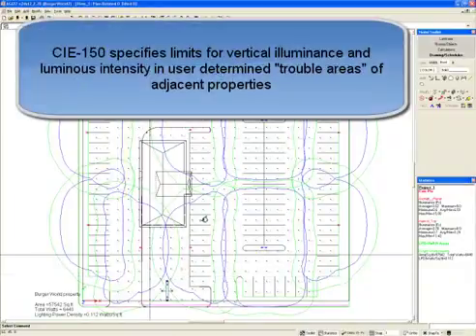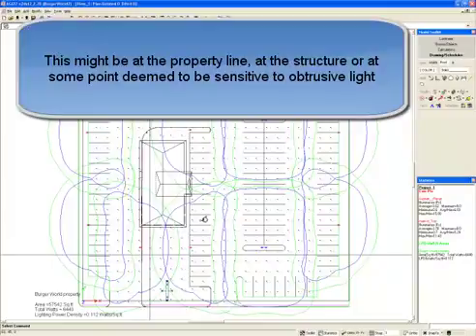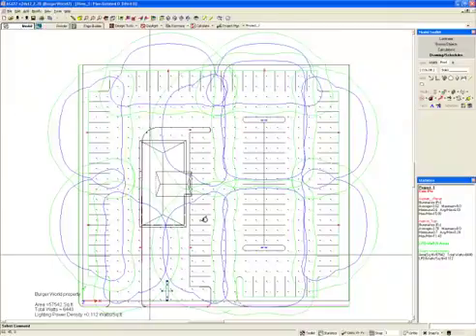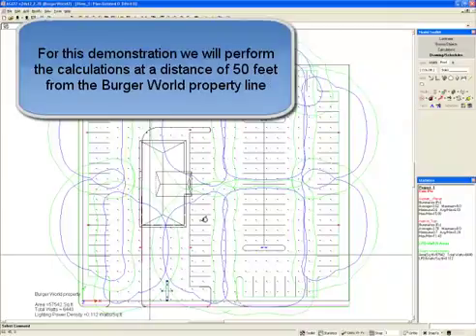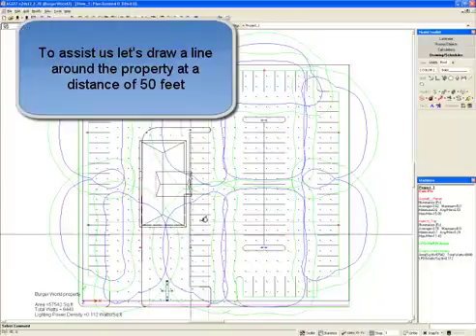CIE 150 specifies limits for vertical illuminance and luminous intensity in user-determined trouble areas of adjacent properties. This might be at the property line, at the structure, or at some point deemed to be sensitive to obtrusive light. For this demonstration, we will perform the calculations at a distance of 50 feet from the Burger World property line.